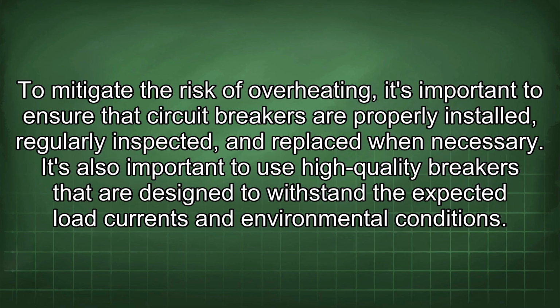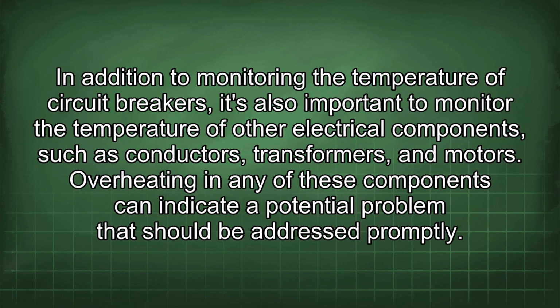To mitigate the risk of overheating, it's important to ensure that circuit breakers are properly installed, regularly inspected, and replaced when necessary. It's also important to use high-quality breakers that are designed to withstand the expected load currents and environmental conditions. In addition to monitoring the temperature of circuit breakers, it's also important to monitor the temperature of other electrical components such as conductors, transformers, and motors. Overheating in any of these components can indicate a potential problem that should be addressed promptly.